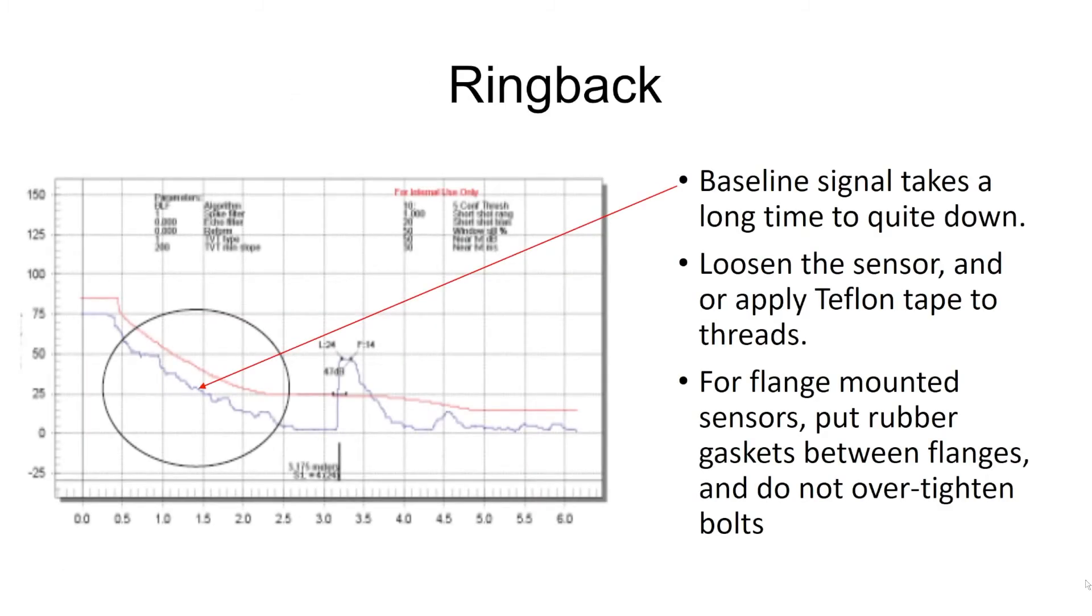The last example we're going to look at today probably represents 50% of the phone calls we get when people are having issues with ultrasonic level controls. It's a phenomenon called ringback. Let's go back to the way these ultrasonic sensors work. The level control sends a voltage to the piezo crystal within the level sensor. It creates noise that wants to quiet down really quickly so it can listen for a return echo.